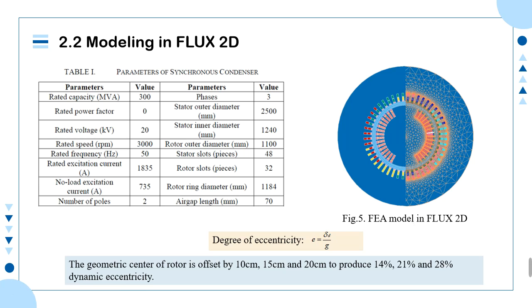An FEA model was built on the basis of Table 1. The degree of eccentricity is defined as the ratio of the offset and the air gap length. The geometric center of rotor is offset by 10, 15, and 20 centimeters to produce 14%, 21%, and 28% dynamic eccentricity.